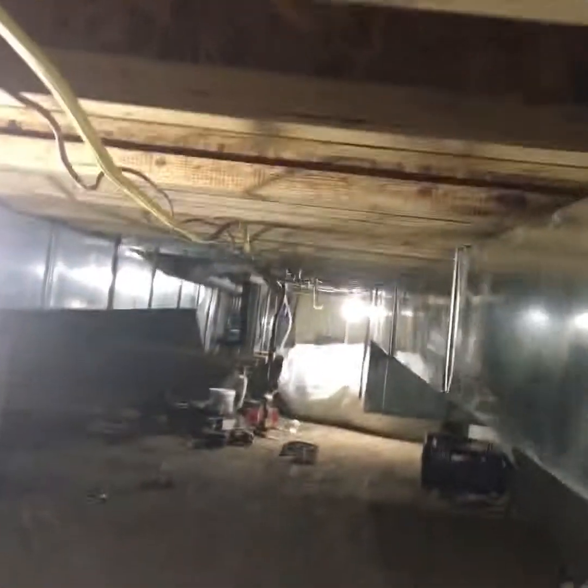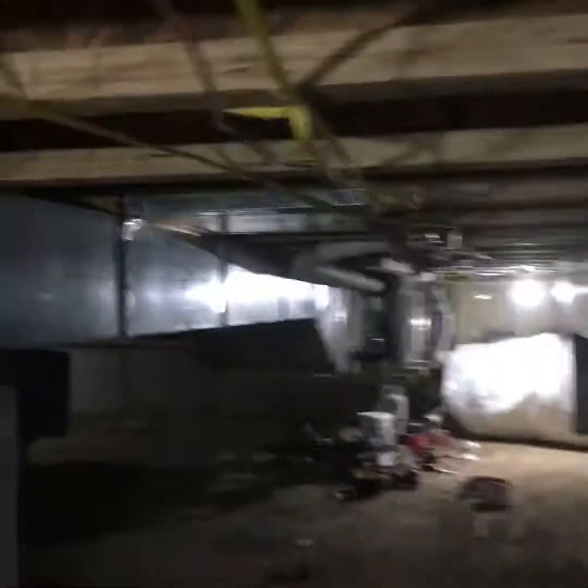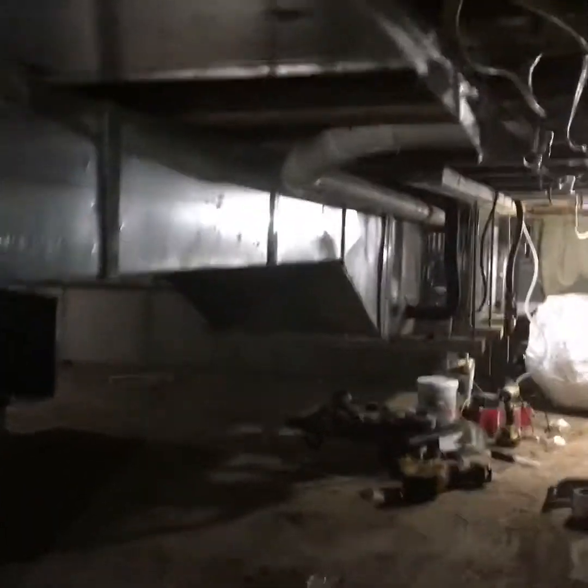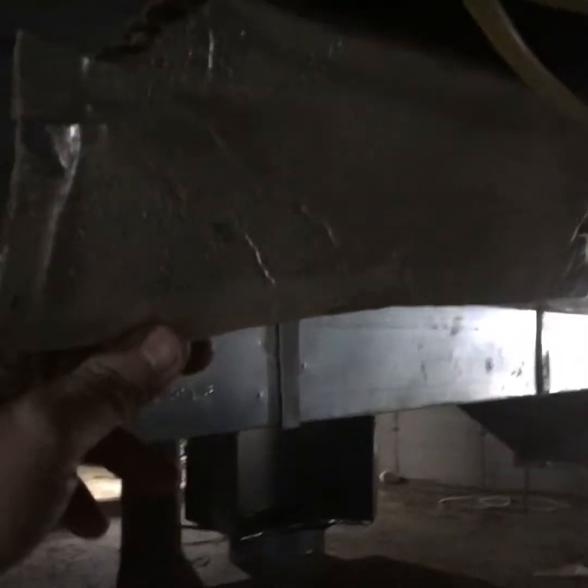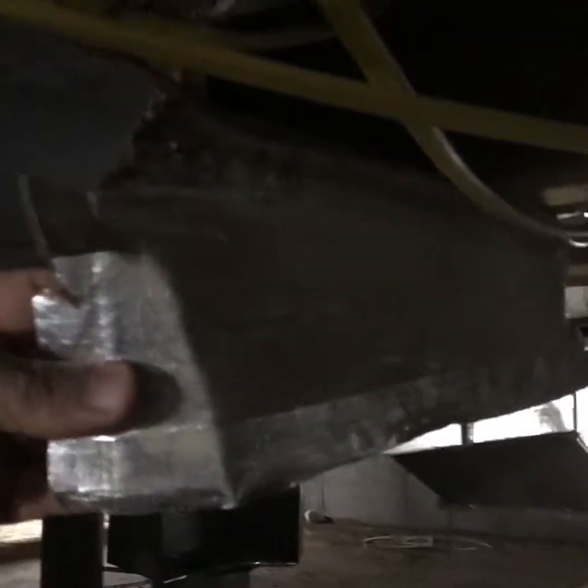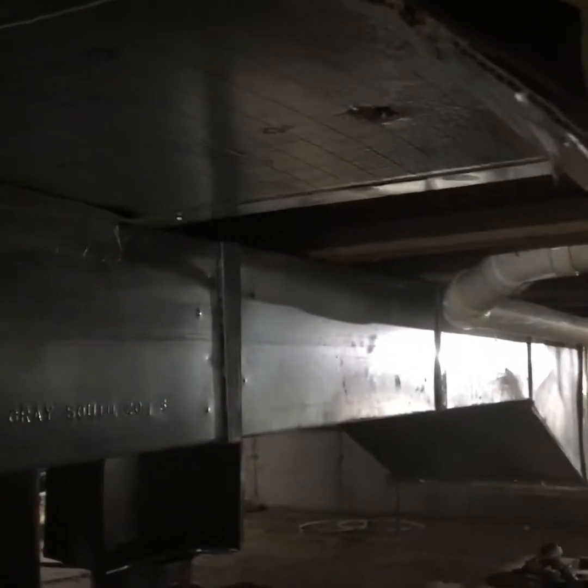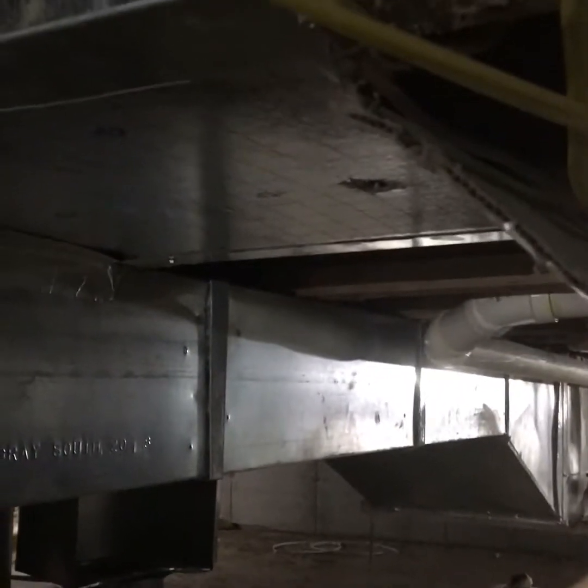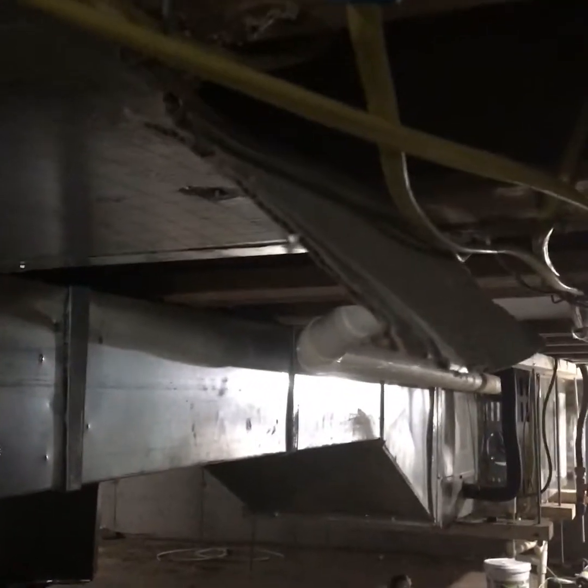I'll show you what the original guys had done. You can see this right here. Sorry about the sound. This is that cardboard. This is made for ductwork. I've never used it, wouldn't use it. But you can, I guess. It has a vapor barrier on both sides, and it's basically made for pan, and you just nail it right to the bottom of your floor joist, and you make your joist space your actual return duct. But they had that set in there, and then it ran across to wherever those 3 1-foot filter back grills were.